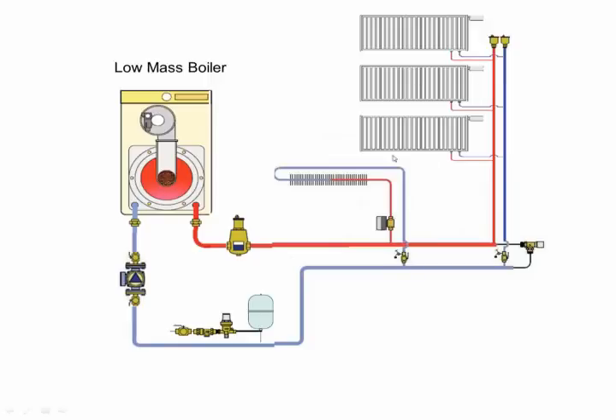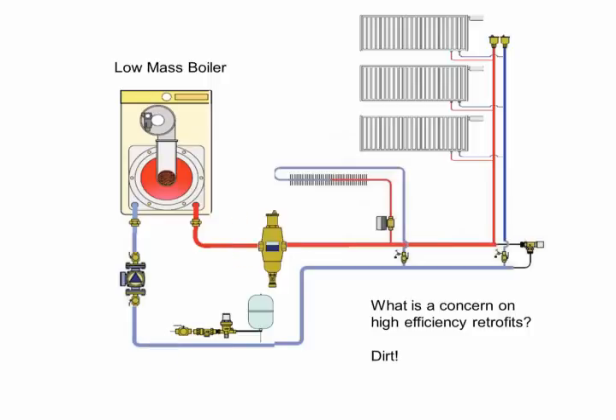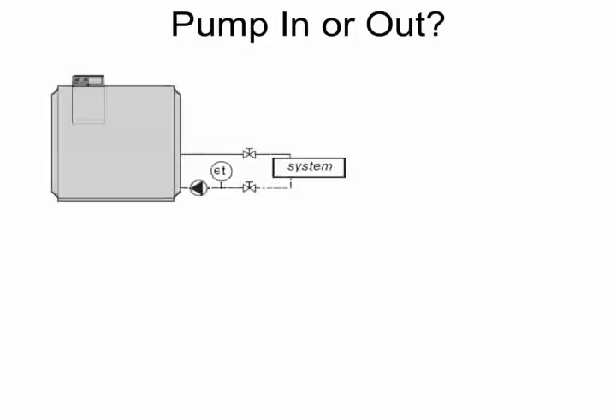Now, the thing about retrofits is that the piping and equipment that you kept in place has already been compromised and is quite susceptible to continuing oxidation and rust floating around in the system. So in retrofits especially, you want to protect your equipment from dirt, such as by using a dirt separator, or a combination device that does both air separation and dirt separation, such as this residential one or a larger commercial one. We'll come back to those in a second.